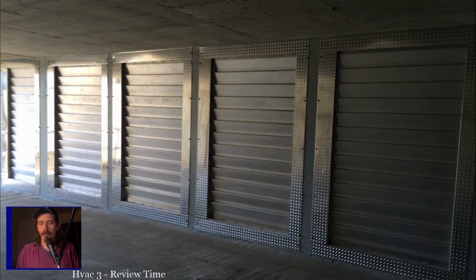The biggest deal on the relays, and I know I mentioned it before that you should probably look at it, but the biggest deal is to make sure that you understand the difference between a single pole double throw or a single pole single throw, and or 3-pole double throw. If it's single pole single throw, you basically have an off and an on position. If it's single pole double throw, you'll have a normally open and a normally closed position. Generally speaking, depending on how the switch is set up, it can be a little bit different than that.